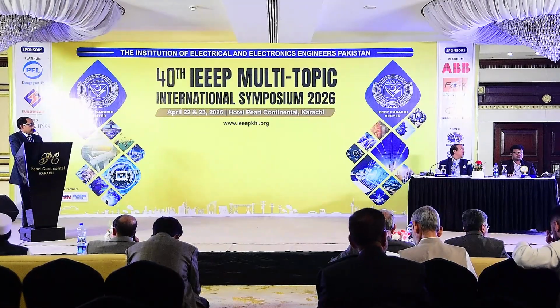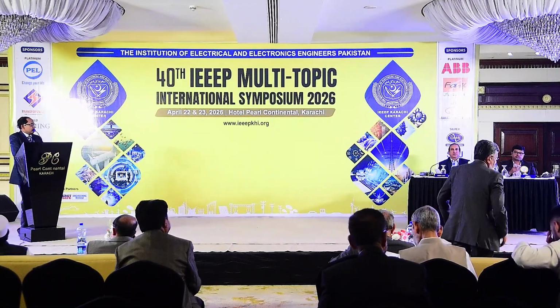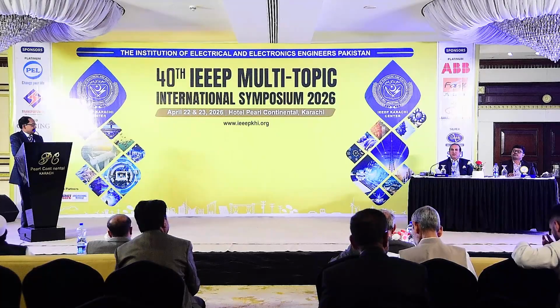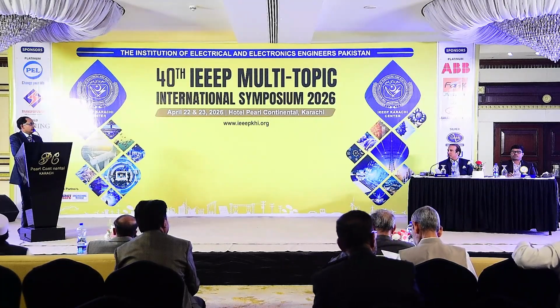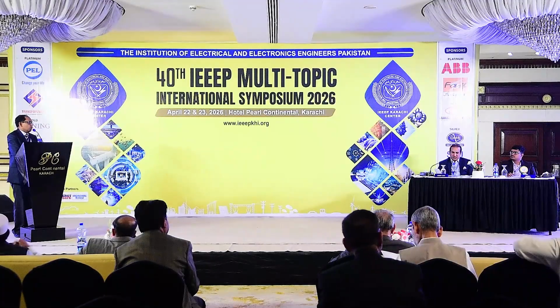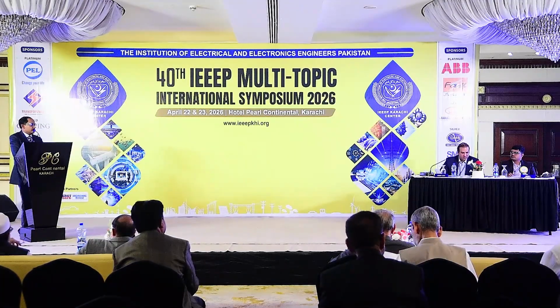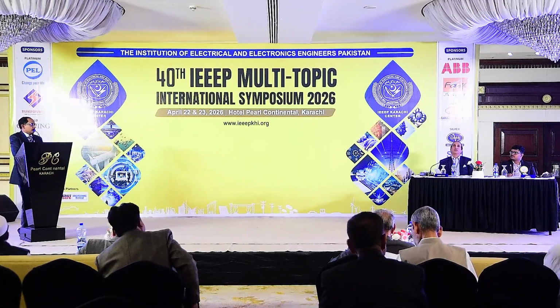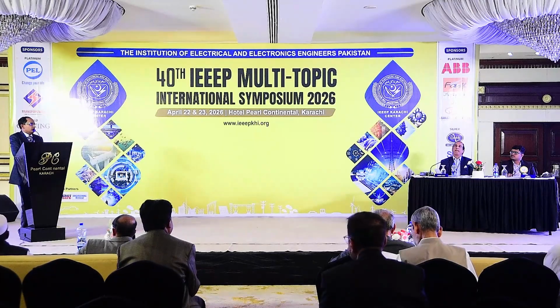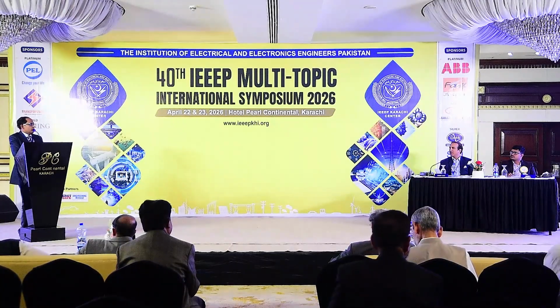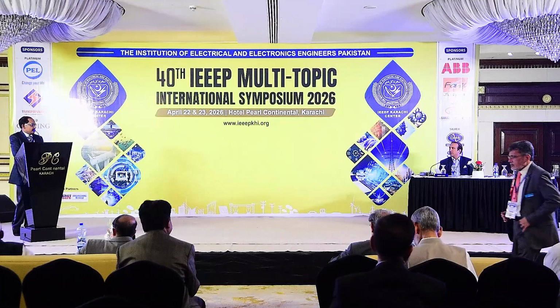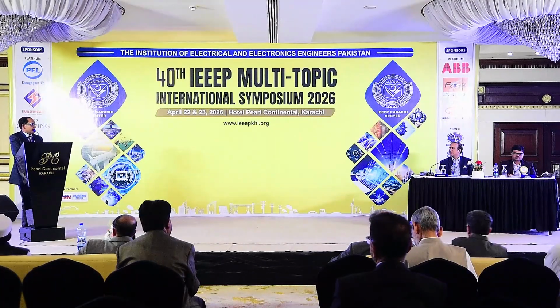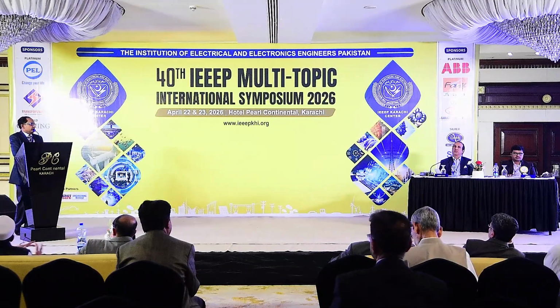One thing I want to mention is that it is not necessary to provide the support from BESS only for critical loads. It can also provide support to non-critical loads, but for that you have to scale the BESS system on a larger scale, which ultimately reflects in high cost. So, in order to keep the model financially economical, the BESS sizing is done in such a manner that the loads are classified as critical and non-critical. Now next.